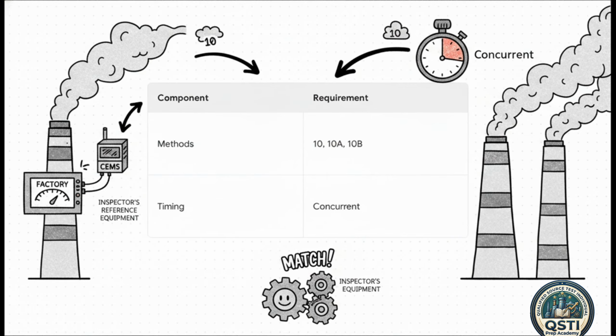To prove the factory's monitor is actually telling the truth, inspectors use approved reference methods, specifically Method 10, 10A, or 10B. But the absolute key here? It's the timing. The sample collection and analysis are run concurrently. That means the inspector's reference equipment and the factory's CEMS are sniffing the exact same exhaust gas at the exact same time. It is literally a direct side-by-side shootout to see if their numbers match up.